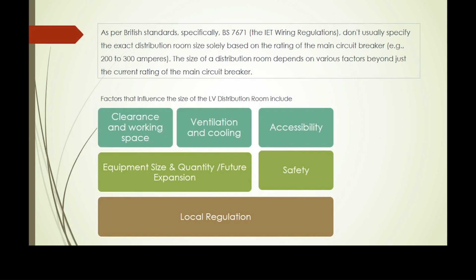Equipment size and future expansion is a very important factor in sizing the LV switch room. The size and number of electrical equipment affects the LV switch room size. The electrical equipment includes switchgear, panels, distribution boards, MCC panels, and capacitor banks. We need to consider each equipment's size when designing the LV switch room.